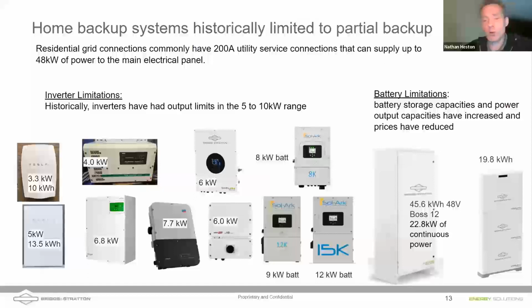Now, that doesn't mean that the Sol-Ark 15K is capable of 200 amps of 240 volt AC service, right? You certainly can overpower the 15K or cause too much of a demand on it so that it overpowers. But we now have the ability to provide for most panels in the US with that 200 amps of pass through, which means we don't need a separate panel. So battery limitations come in here as well. People often think of the battery, of how long it's going to last in an outage, but they don't think about the power limitations.